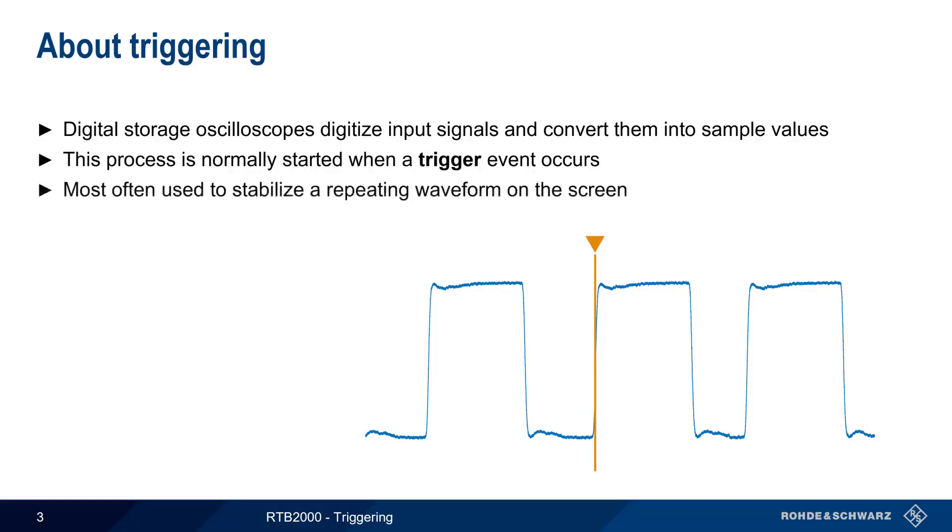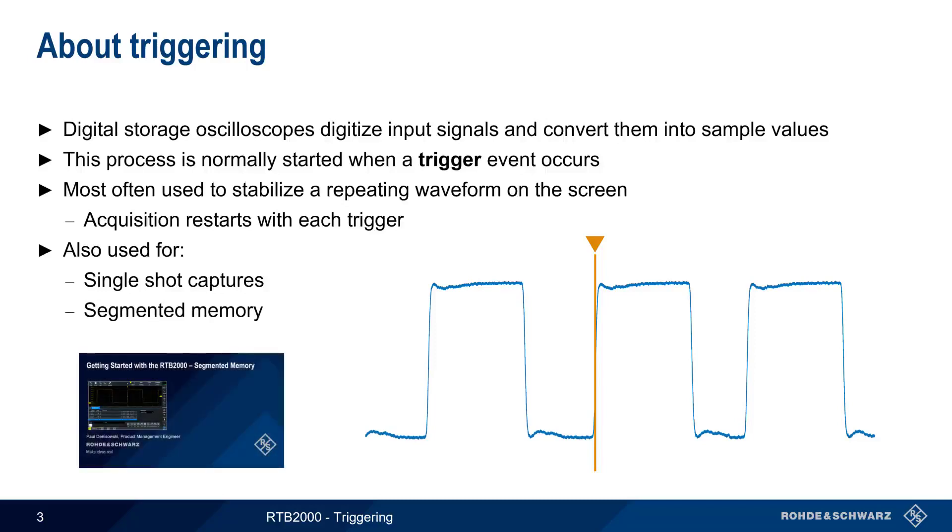The most common application for triggering is stabilizing a repeating waveform on the screen by starting a new acquisition with each trigger event. Triggering can also be used when making a one-time or single-shot capture, and is also important in segmented memory applications. Please see the separate presentation on segmented memory if you'd like to learn more about how to use segmented memory on the RTB.